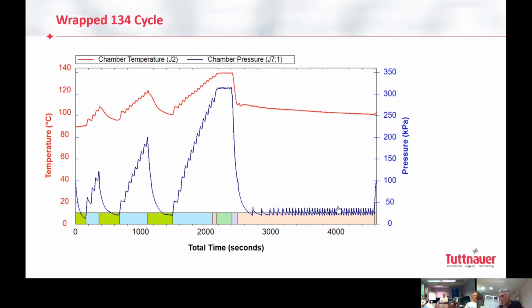That's why we're using these pulses. Why do we use these pulses? One, to transfer energy from the wall, because once new air is coming, it is dry air. Outside in the room, in the clinic, there is maybe 20% humidity, air condition, it's dry air. Fresh, cold air coming into the chamber, absorbing the ambient, which is 99% humidity. The chamber is full of humidity after the cycle. This dry air absorbs, then it goes out, kicked out by the vacuum. So you see the pulses here and there, here and there. New air comes and removes.